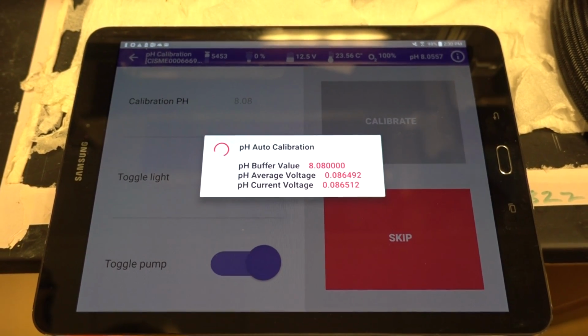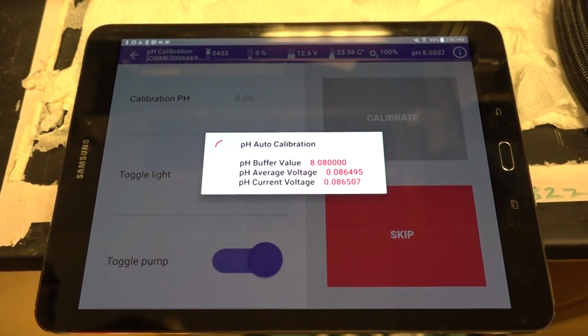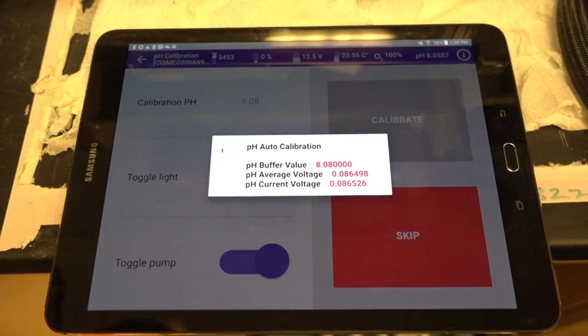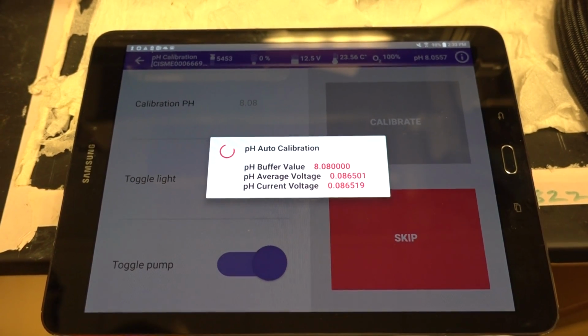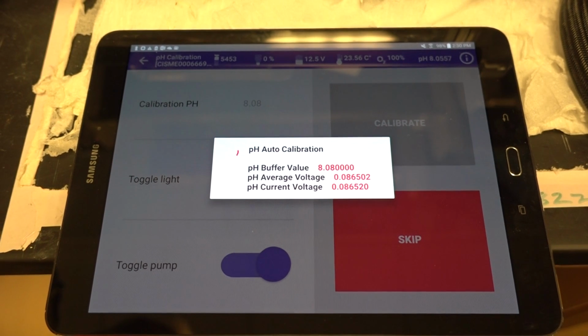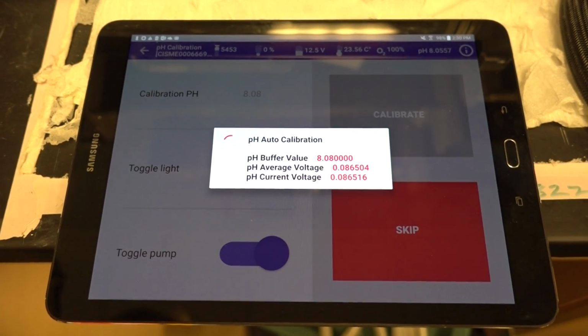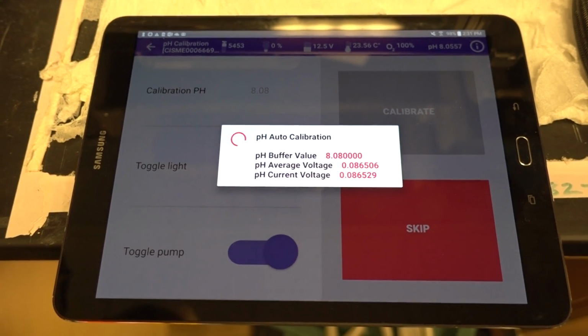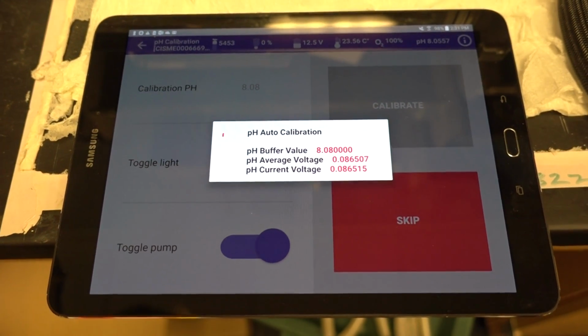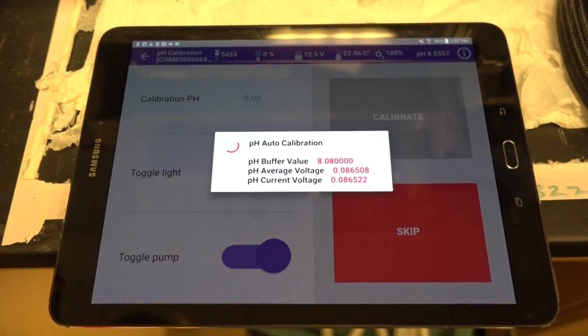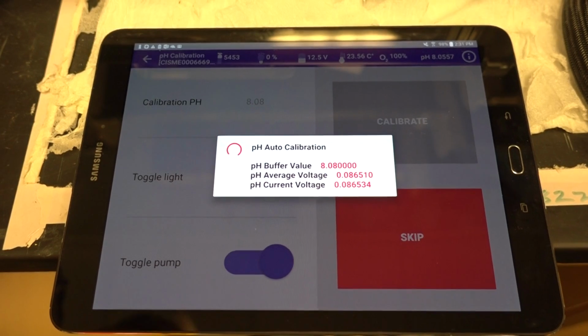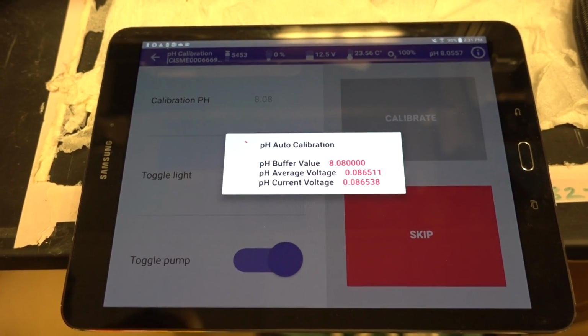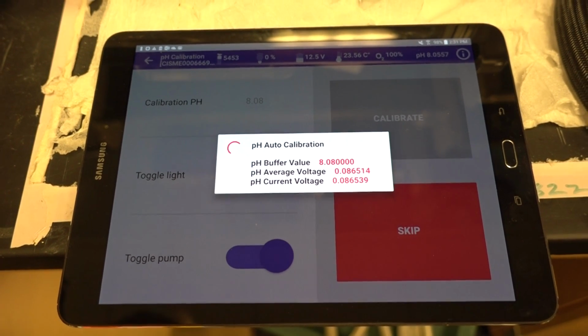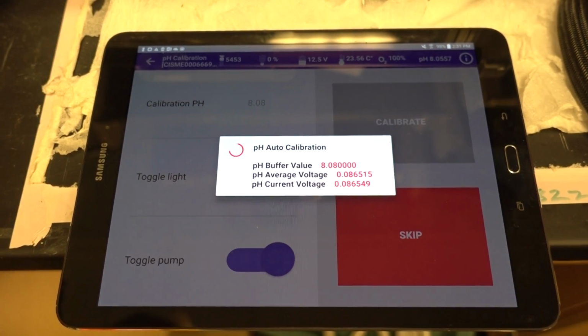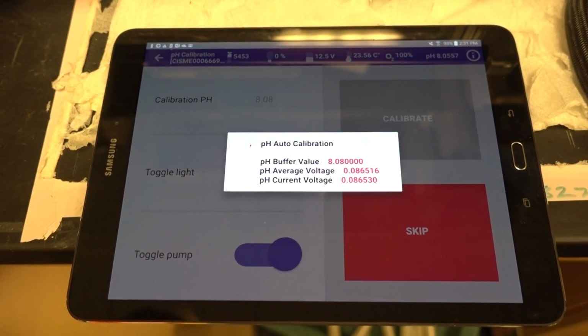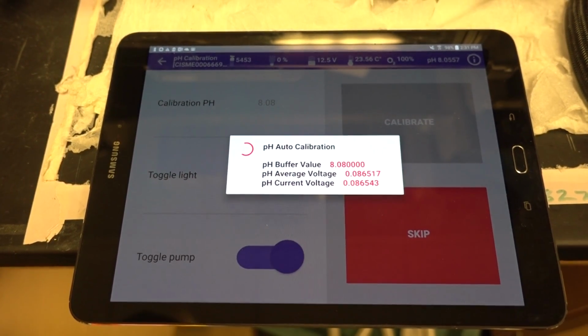Very importantly, the electrode should have been powered up for at least 1 hour in the buffer solution that you're using before you attempt this calibration. Once you've calibrated the electrode, in our experience, it is very stable for long periods of time. When we do field work, we calibrate the electrodes back in the laboratory, pack them up, ship them to the field, and we do a cursory check of the pH with a separate pH meter just to make sure nothing has changed, but we've hardly ever had to do any type of recalibration in the field.